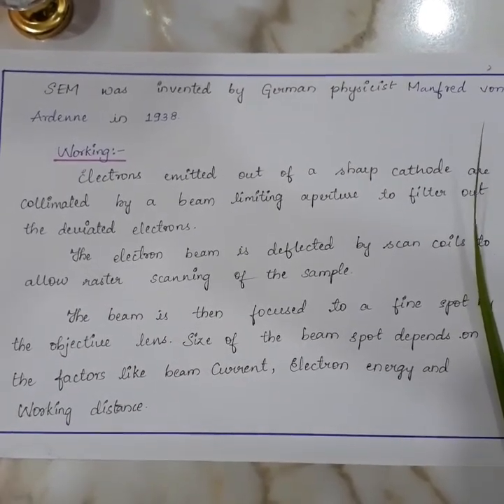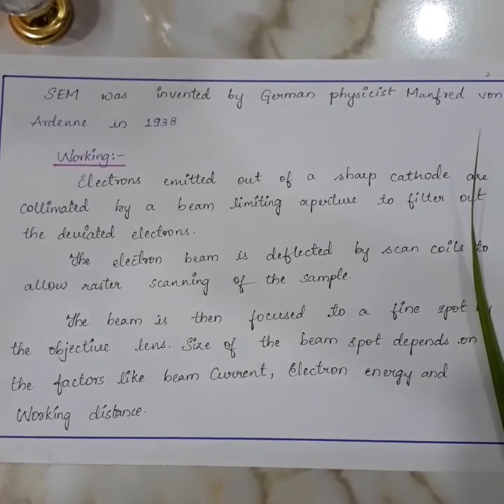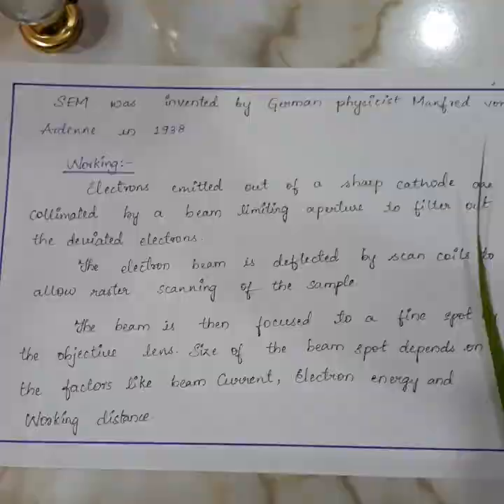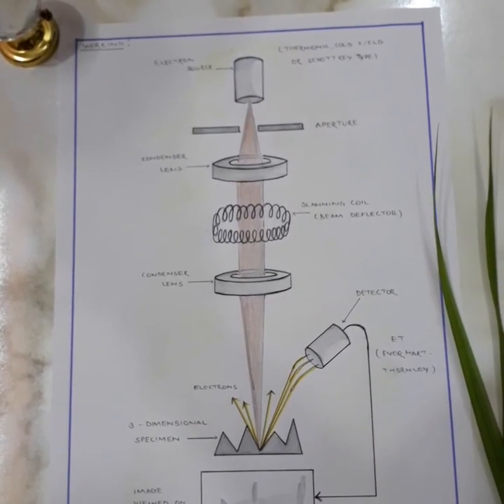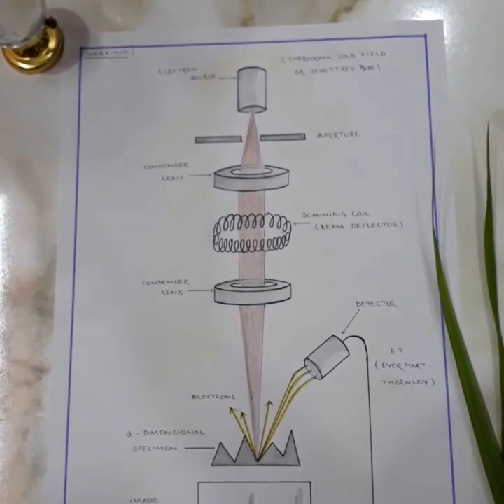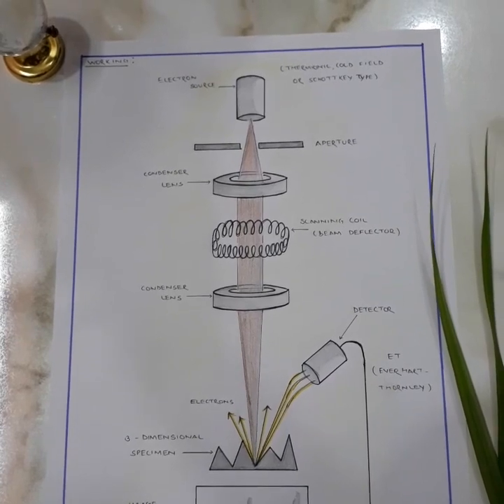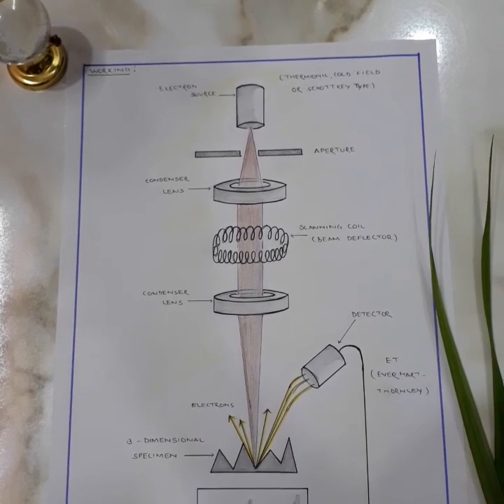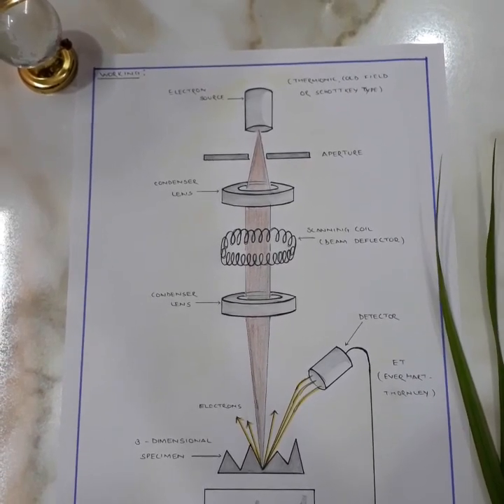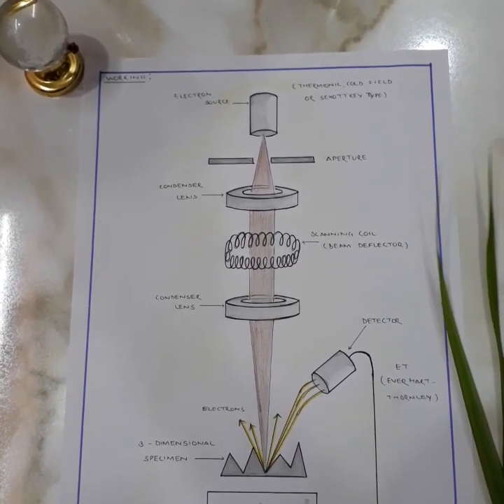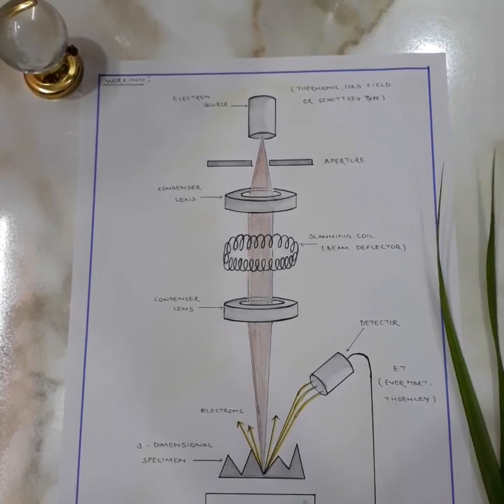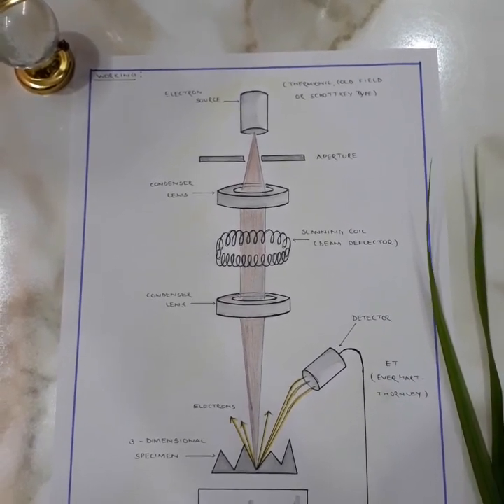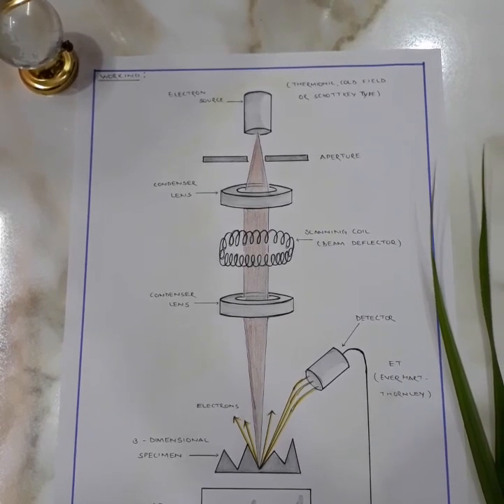The size of the beam spot depends on factors like beam current, electron energy, and working distance. This diagram shows how an SEM works. After the electron beam is focused to a fine spot by the objective lens, a detector detects different signals resulting from the interaction of the electron beam and sample. The detector signals are recorded pixel by pixel during the scan and collated to create an image.